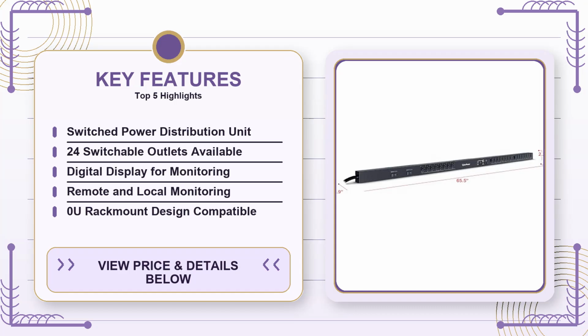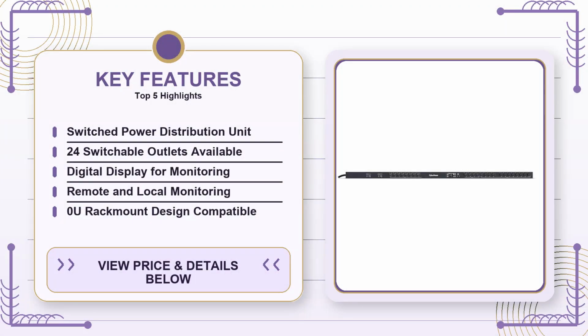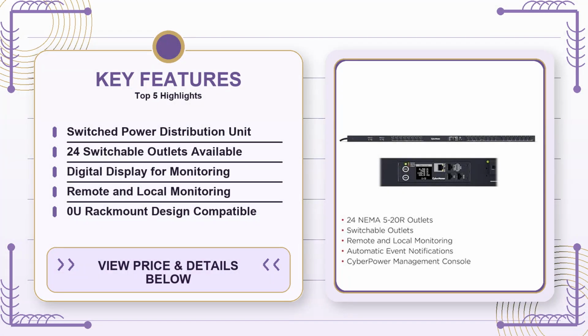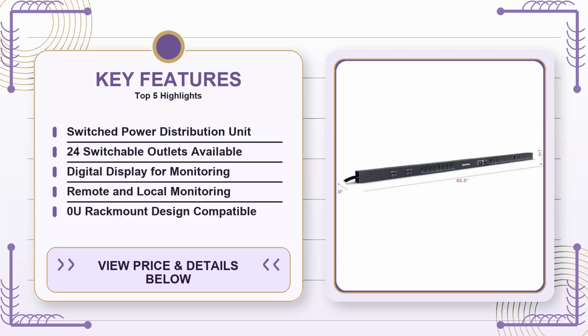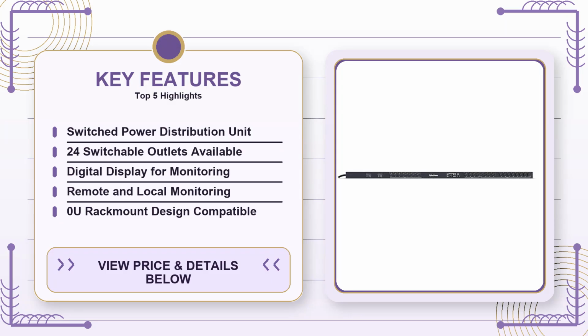Remote monitoring is another strong point. CyberPower's built-in Ethernet interface lets you connect the PDU to your local network, and you can view status and control outlets through their web console or SNMP-compatible monitoring tools. For IT admins who already have a network monitoring suite, this means you can pull the PDU into the same dashboard you use for servers and switches. If a device starts drawing too much current, you'll get an alert and can shut that outlet off before a breaker trips. In a small lab where you're experimenting with different configurations, that level of control can prevent a lot of frustration.